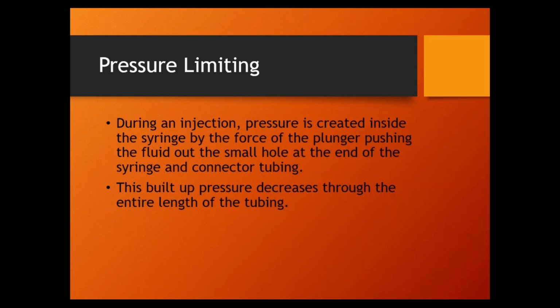800 psi. Now let's just do 100 psi. They don't understand the concept of the pressure limiting. So what's going to happen is they can make a pressure limit way too low. They start the injection, the injector hits its pressure limit, and it slows way down, because the flow rate is what's determining the pressure. Then the operators, if they're paying attention, will call in and say the injector's not injecting properly, shooting way too slow. If they really don't know what they're doing, they'll say my image is too dark. Well, the image is too dark because the contrast we expected to get to the patient is not getting to the patient. So they're not even noticing the injector's not injecting properly.